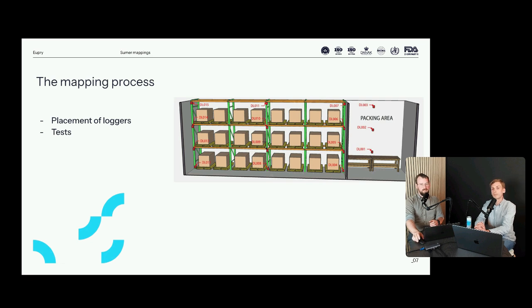Another part is choosing which type of tests to do. You might have heard of stability tests, where you leave the facility alone and let it run for 1 day, 3 days, 7 days, whatever is suitable, both empty and loaded. There could also be power failure tests, where you see what happens if power fails and how fast you need the HVAC system back up. Normally we'd also see door opening tests, opening doors for predefined amounts of time and frequency, then seeing how that influences the stability and homogeneity of temperatures within the facility.